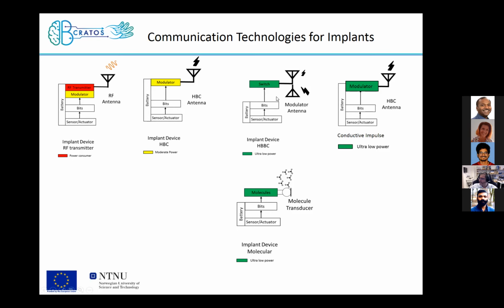So one is using backscatter communication. Backscatter communication is a method that uses a radar approach, in which a radio signal is sent from outside the body toward the implant. And then the implant alters the amplitude and phase of the radiation, controlled by the data source. And then the reflections can be picked up externally. In this way, the implant system will not have extra circuits for communication, no electronics for RF generation, and also a MEMS switch, a very low power mechanical switch, can be used to alter the antenna impedance.